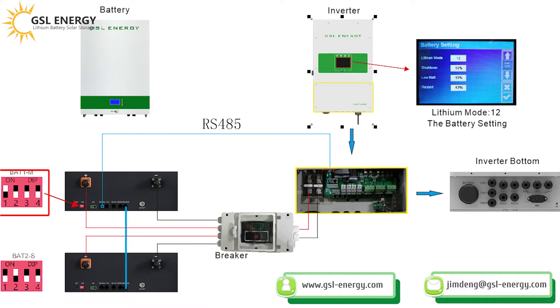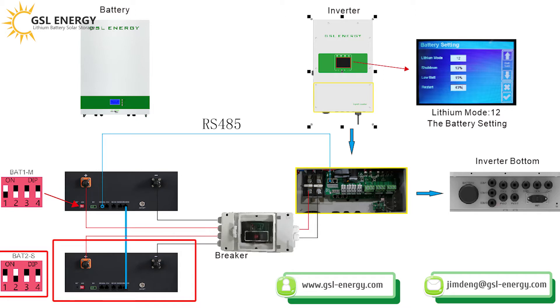The third step is the battery DIP switch settings. For the main battery: switch 1 is up, switches 2, 3, and 4 are down. For the slave battery: switch 2 is up, switches 1, 3, and 4 are down.